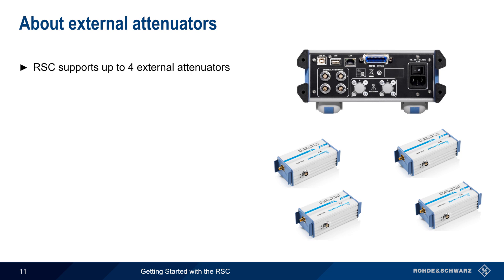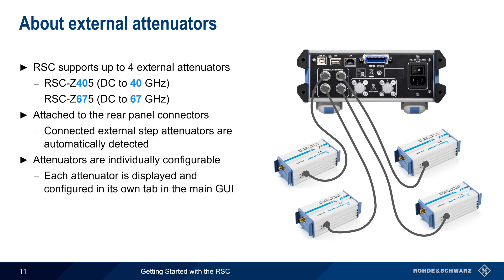Now let's come back to the topic of external attenuators. As mentioned earlier, the RSC supports up to four external attenuators in addition to its internal attenuator. The two external attenuator types are the RSC-Z405, which goes up to 40 GHz, and the RSC Z675, which goes up to 67 GHz. These are attached to the rear panel of the RSC and are automatically detected when attached. Each attenuator can be individually configured and viewed through the main GUI using the select key to cycle through each attenuator's tab. Note too that correction data for each sensor is stored within the sensor and is automatically read when the sensor is attached.